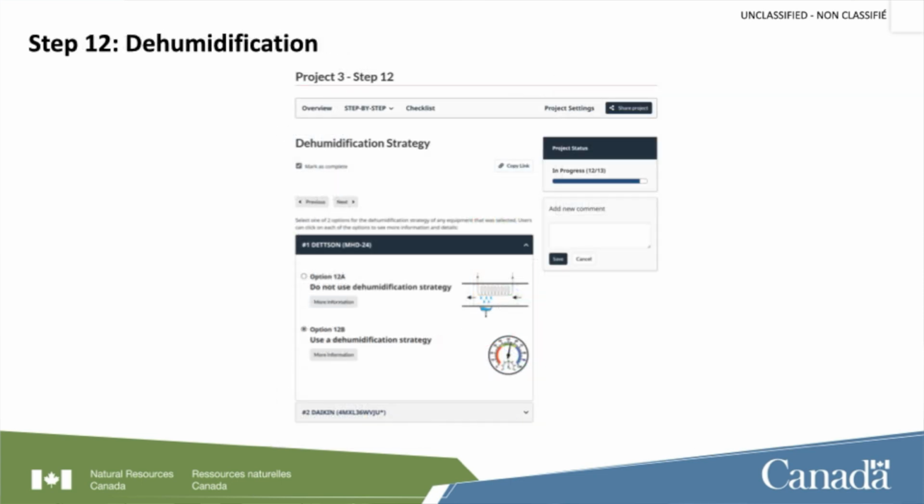Dehumidification strategy. Do we really need that in the province of Alberta? Absolutely, for AC, sorry, my bad. The AC is going to take care of that. Do we need dehumidification any other time of the year? No. So the dehumidification strategy is looking for any extra dehumidification that you require. It's HRV for winter. Yeah, they're not talking about HRVs. They're actually talking about putting some kind of an actual dehumidifier in.